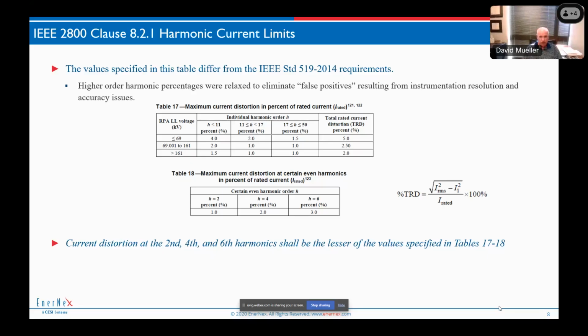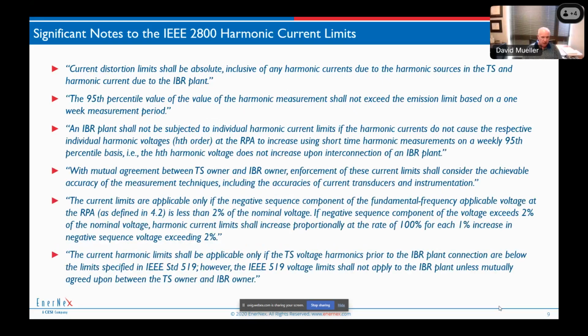These limits are very relaxed from what it was from 519, where we have percentages of a percent that had to be met, and we were finding that we were getting in the limits in the milliamps that we couldn't even measure accurately. And so the effort here was to make limits that were reasonable, limits that we could reasonably measure, and oh, by the way, limits that can be met, because the IBR plants are generally fairly low sources of harmonics, generally can meet these limits, and we're pretty much done. We can show that it's not causing an effect.